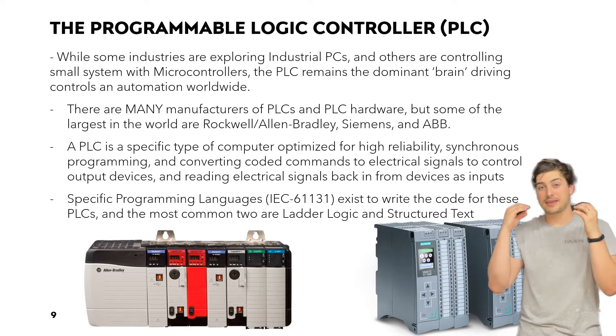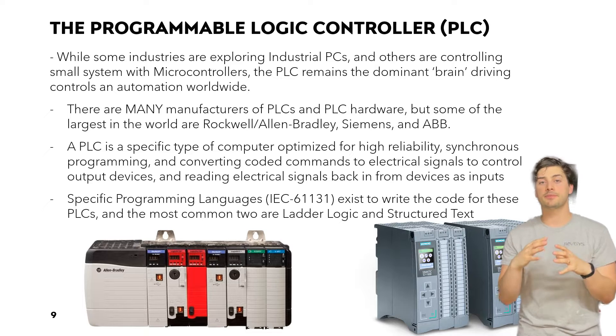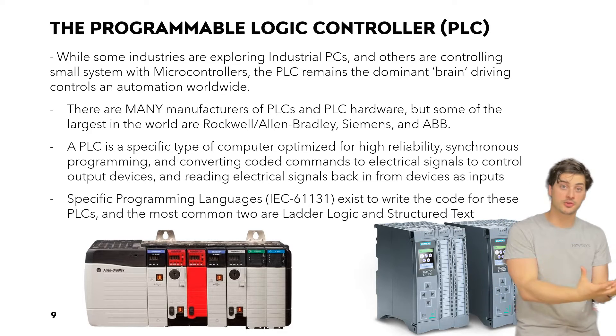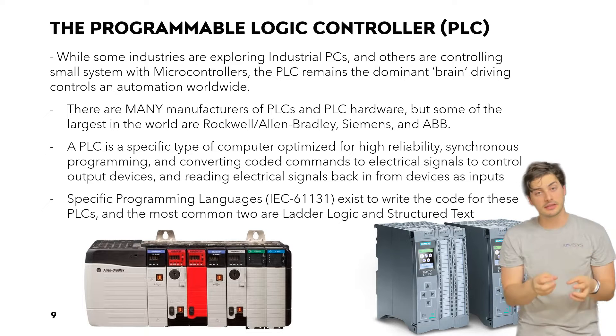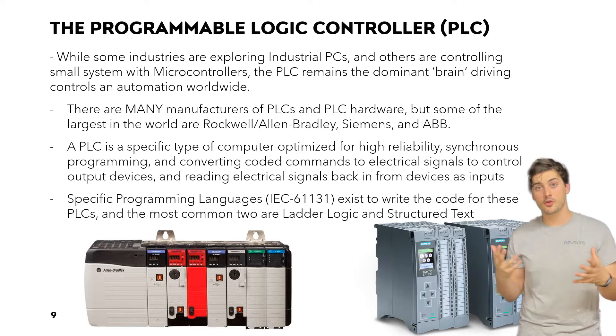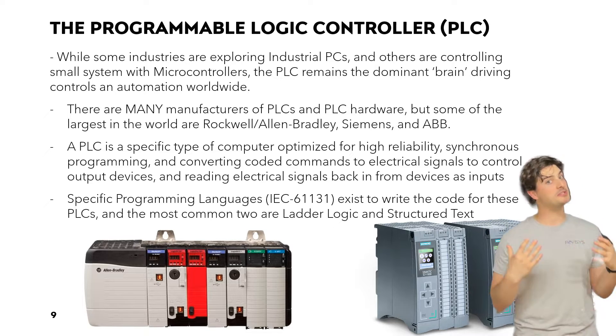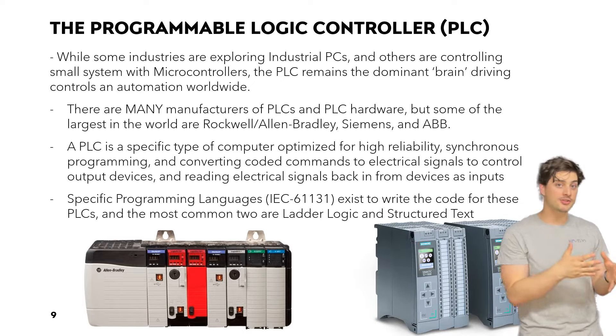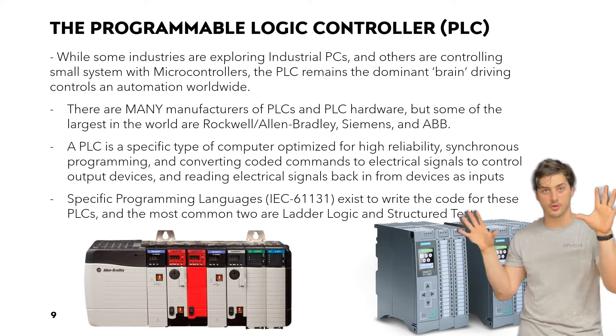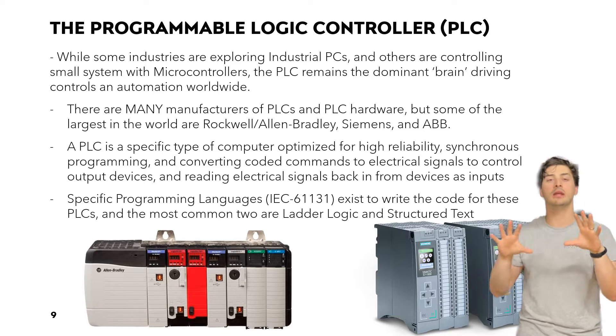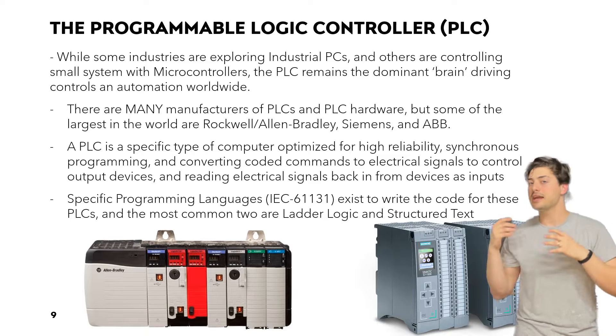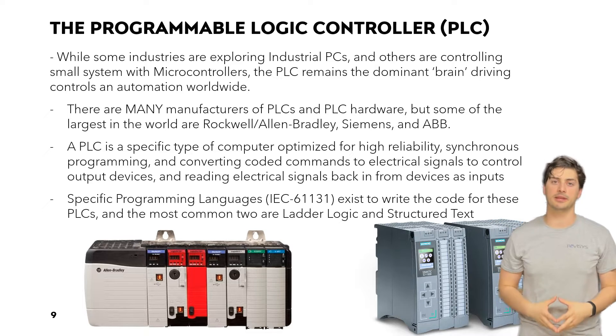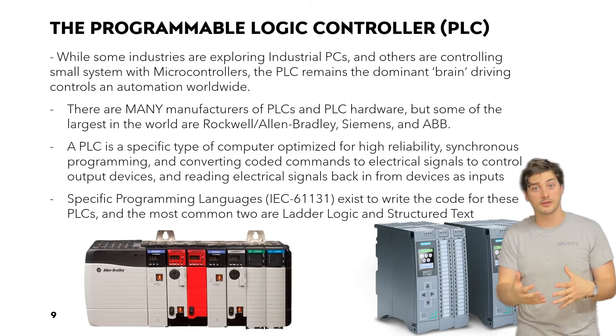A PLC is a specific type of computer optimized for high reliability, synchronous programming — meaning time-cycled code — and converting commands to electrical signals to control devices known as outputs, and reading electrical signals back from devices known as inputs. Specific programming languages exist to write code for these PLCs. The most common two you should have on your radar are ladder logic and structured text. Ladder logic looks a lot like relays — a very visual, flowchart-like language combining programming and electrical concepts. Structured text is somewhere between C++, C#, and Python — a more traditional programming language where people with a software background often feel more comfortable.